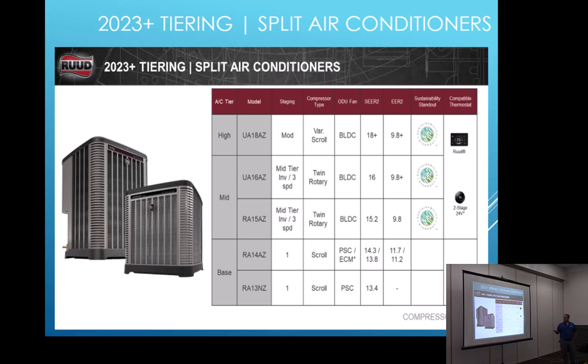Twin rotary compressor. All three have a brushless DC fan motor. Okay? Not a PSC motor anymore, not an ECM. It's a brushless DC fan motor. The RA14AZ, which we have, we do not stock the 13. It's not in our area to be able to sell. But the 14 has a single-stage scroll compressor with a PSC or an ECM motor. The 5-ton has the ECM motor. Everything else has the PSC fan motor in it.